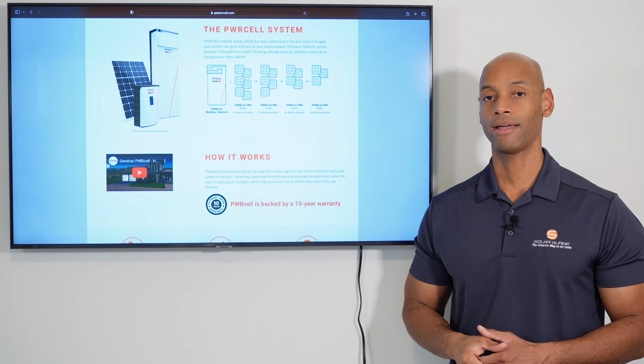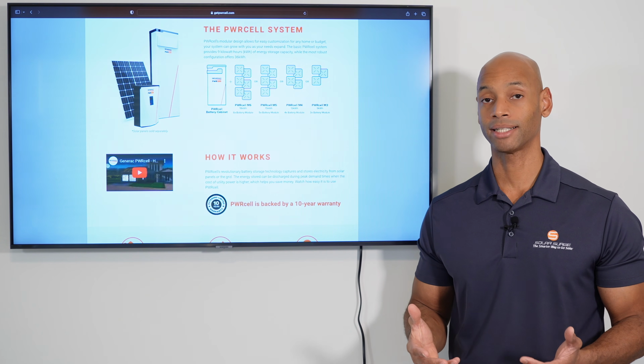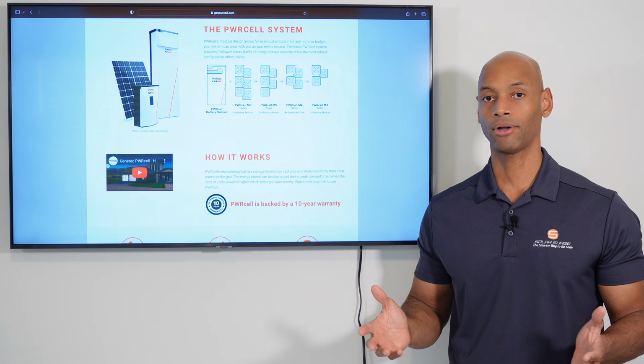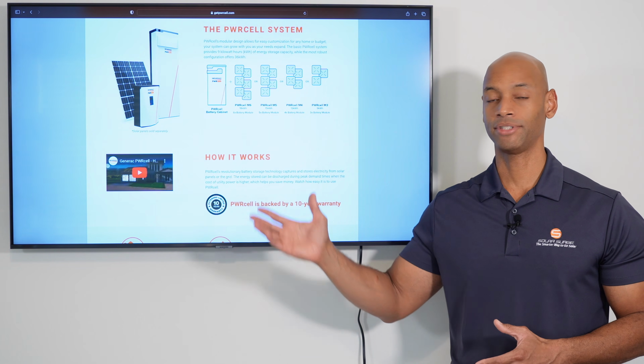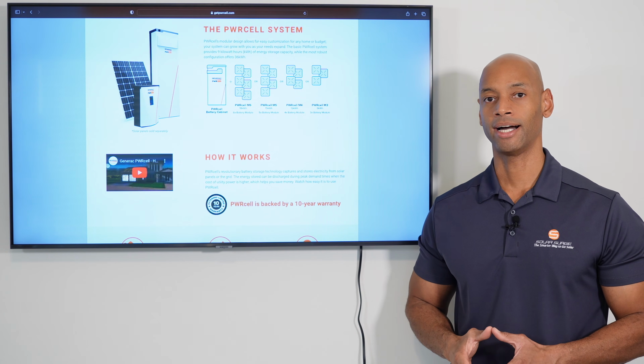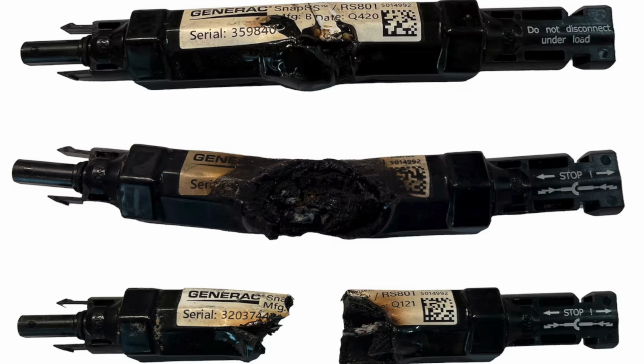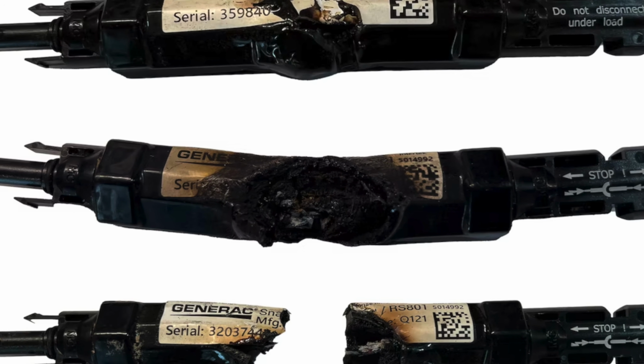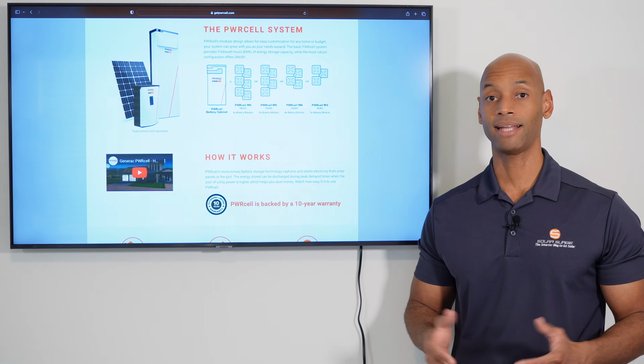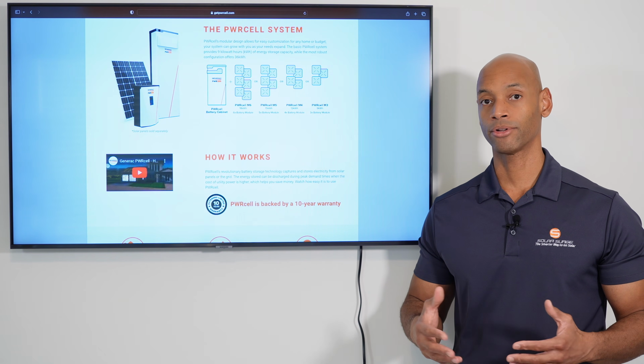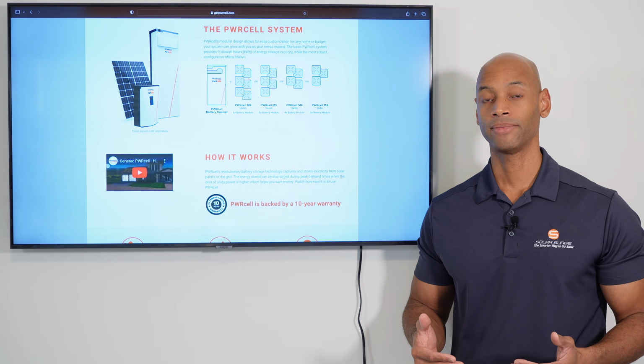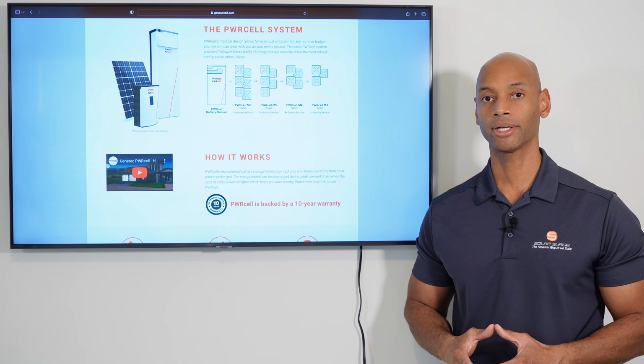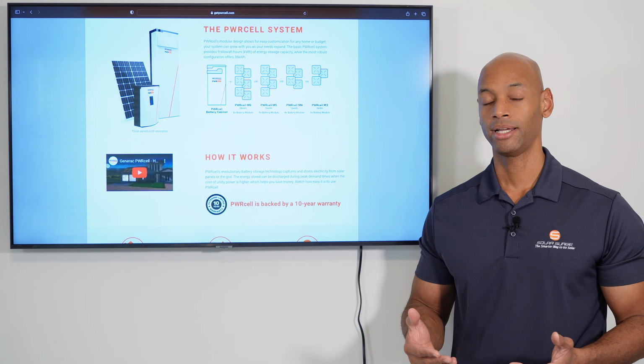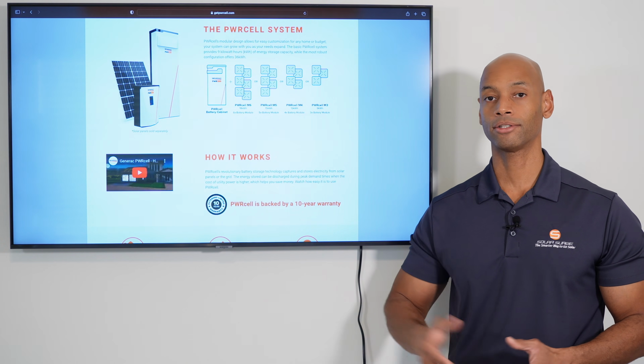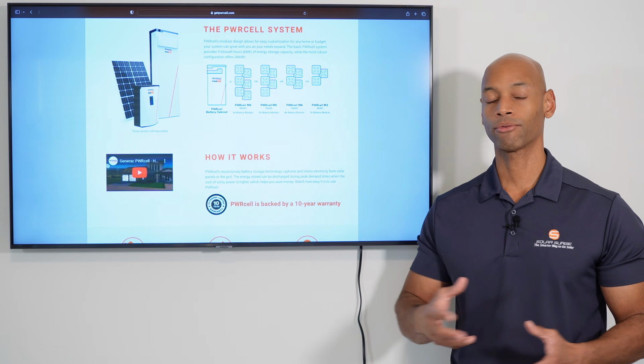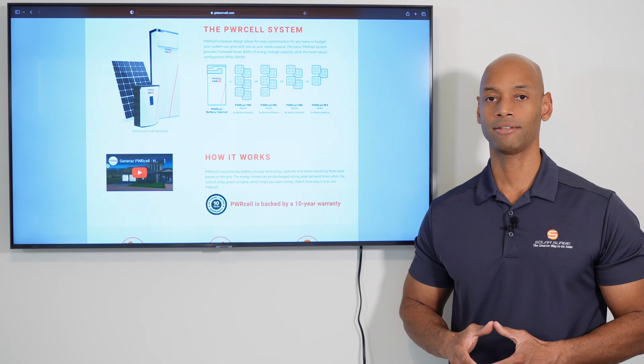Now the problem is that those Snap RS devices were overheating and melting, causing normal functioning solar systems to cut out. You may have seen some pictures of what these Snap RS devices look like when they've overheated and burned out. These devices failed by the tens of thousands, meaning not only were there tens of thousands of upset homeowners whose solar systems turned off when they should have been working, but the installer had to send their installation or maintenance crew back out to these homes, get back on the roof, pull up the solar panels, and change out these defective devices.